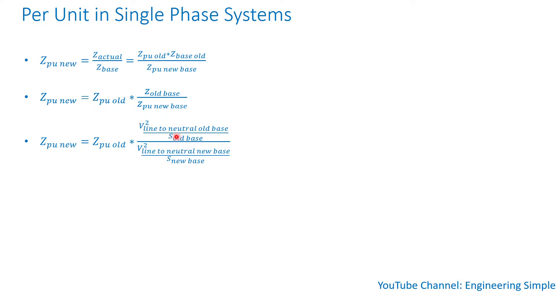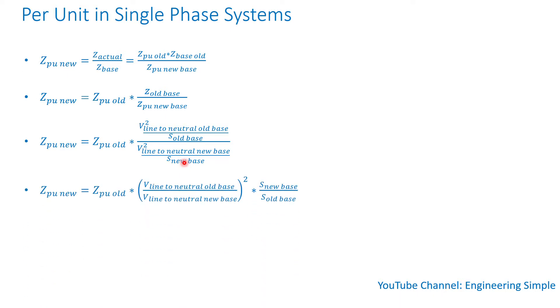Since impedance equals voltage squared divided by apparent power S, I substitute each base impedance with voltage squared over S. You can see it's old base over new base — so instead of using impedances directly, I use voltage squared divided by apparent power. After rearranging, the per unit impedance on the new base equals the per unit impedance on the old base times the line-to-neutral voltage on the old base divided by the line-to-neutral voltage on the new base, squared, times the apparent power on the new base.